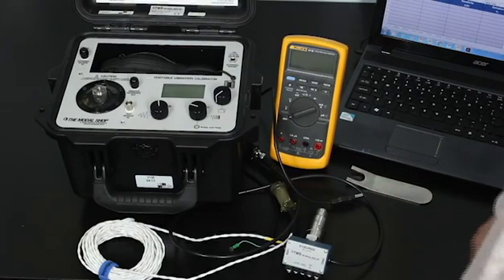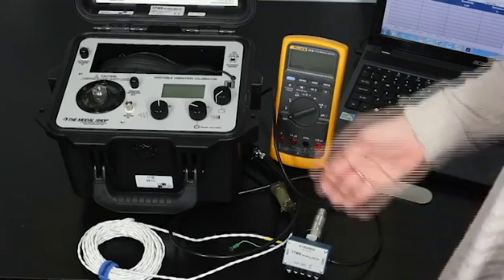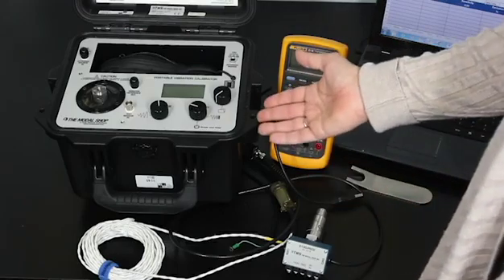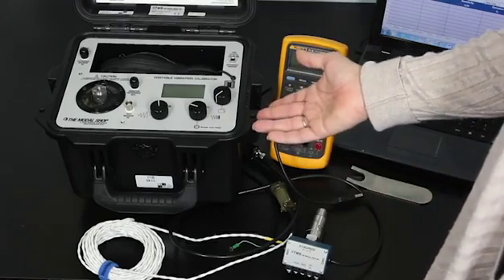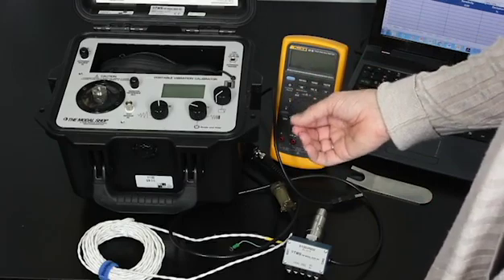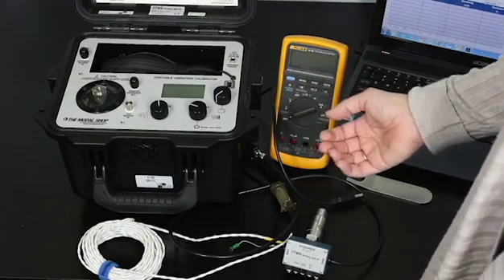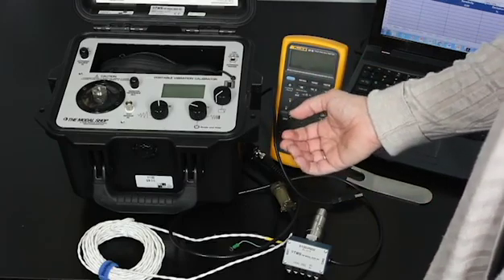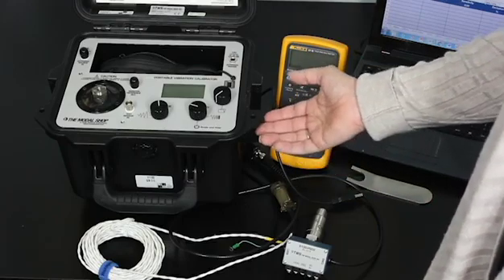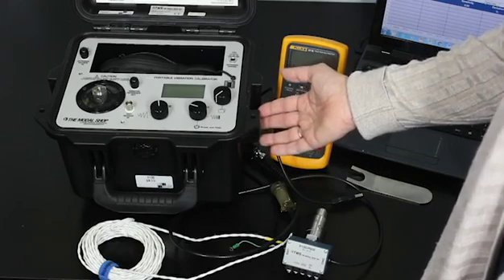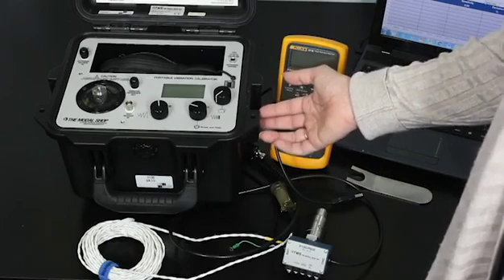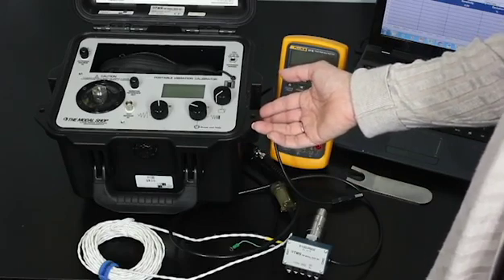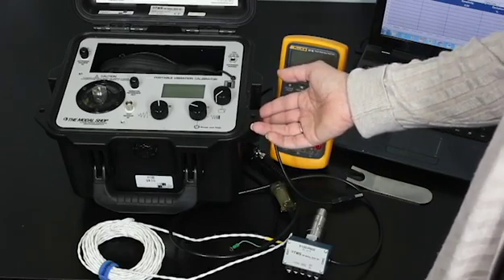To do this, I'm going to be using the model 9110D portable vibration calibrator, although the same procedure could be performed with the 9100D. This is a compact and self-contained vibration reference source, and its frequency response goes down to 5 hertz.